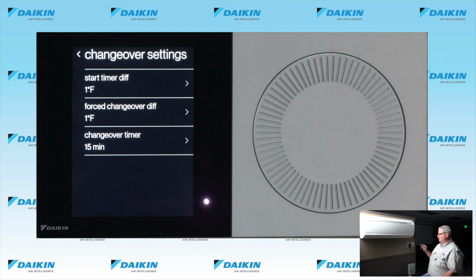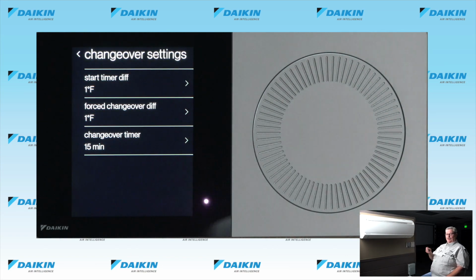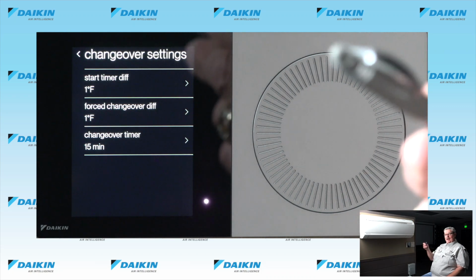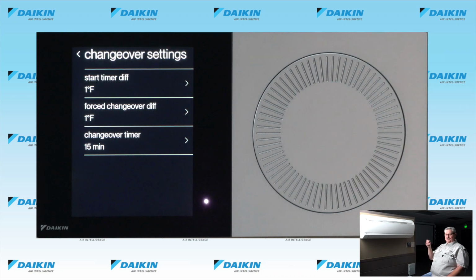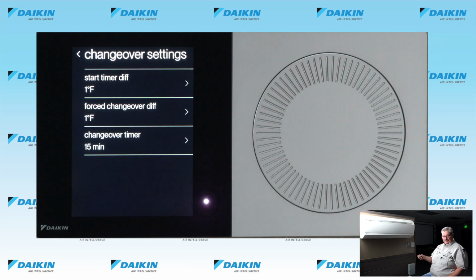And then there's one other function, the force changeover differential. So if we've already exceeded 1 degree past set point to change the reversing valve, and then we set a timer on top of that, if the temperature increases or decreases by 1 more degree, it will override the timer and start the function. That's our heat and cool.